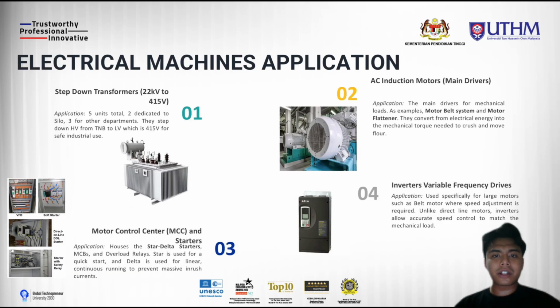This is the electrical machines application. So the first one is the step-down transformer. The facility uses 5 transformer units to step down the 22 kV high voltage from TNB down to a safe 415 volt low voltage. This stepped-down power is then distributed to the motor control center.